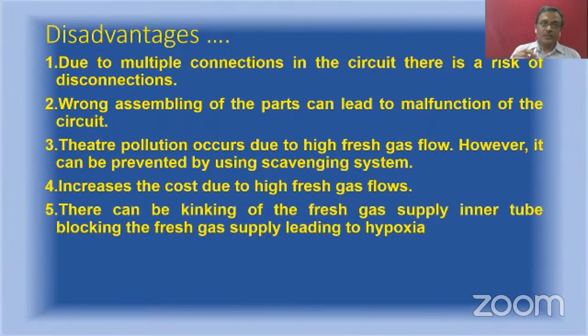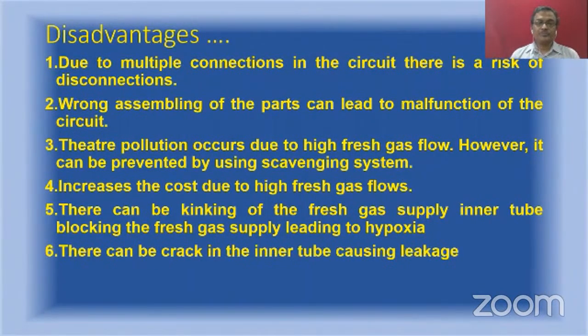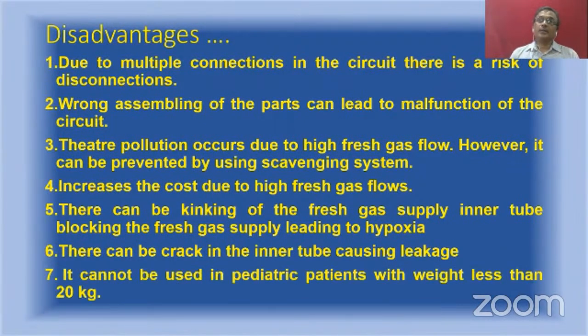And if the inner tube is kinked, no gas will reach the patient and can put the patient at risk of hypoxia. And a crack in the inner tube can cause leakage and can extend the dead space and can cause dangerous hypercarbia. And it cannot be used in children below 20 kg.